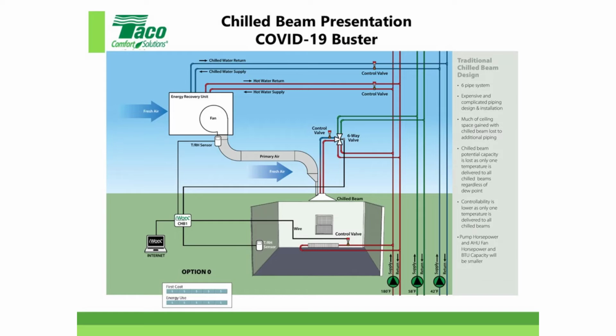Now you got that water going around the building, right? And going over to a 6-way valve or something to the chill beams as well. That's all it services, is the chill beams, the radiant cooling. And then you need cold chilled water to go around to get to fan coils or to your energy recovery, the dedicated outside air unit. So you start looking at it. So that's option 0 that a lot of people have.